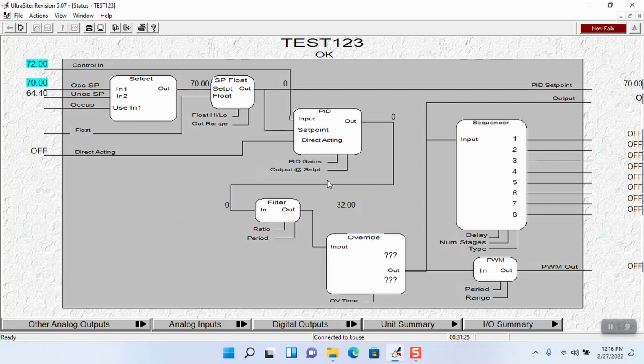You need a steady rack. You don't want the suction compressor cycling on and off. You don't want condenser fan motors cycling on and off. So try to keep the suction as steady as possible when you're doing it. Keep the rack loaded up. That way you can tune this loop how it should be running, and then check it after, while everything else is running. So it all depends on what you're doing. You just got to take that and run with it.